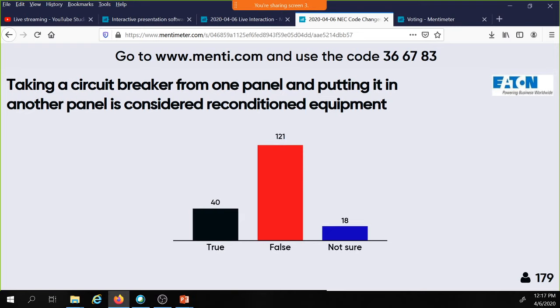We're always permitted to - no matter what facility I'm in, whether it's in my house, on the other side of the wall here, my panel board - if I take a circuit breaker out of commission, put it on the shelf, and add another circuit later, I can reuse that breaker, if it was perfectly fine, was doing its job, and will continue to do its job. If I decide to take that breaker apart, now I'm into the discussion of reconditioning it, because you're taking it apart, making a change, because it was not working, and now you're bringing it into working condition. We're going to talk about reconditioned equipment as part of this program.